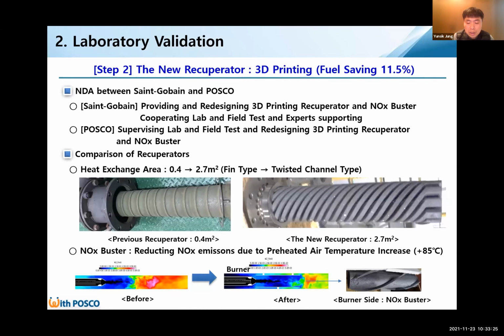The newly designed recuperator has much more heat exchange surface area compared with the previous version. The fin-type heat exchanger has 0.4 square meters of heat exchange area. The new one has 2.7 square meters of heat exchange area. In addition, the NOx Buster is installed and tested to reduce NOx emissions caused by the preheated temperature increase.